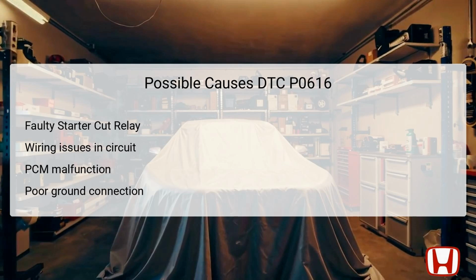A malfunctioning PCM could also incorrectly interpret the information from the relay, indicating an error where none exists. Moreover, a poor ground connection can result in voltage drops, affecting the relay's ability to function correctly. Each of these possibilities should be investigated during the troubleshooting process to determine the root cause of the issue.